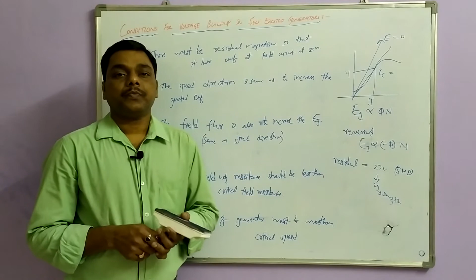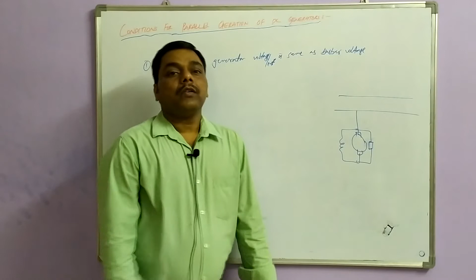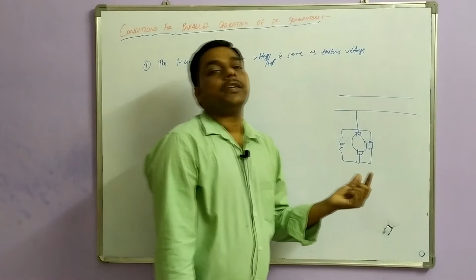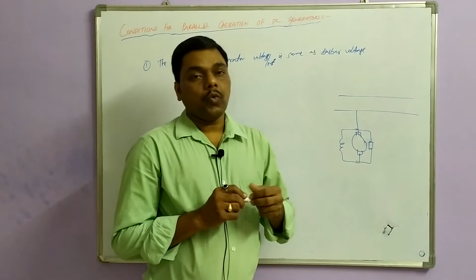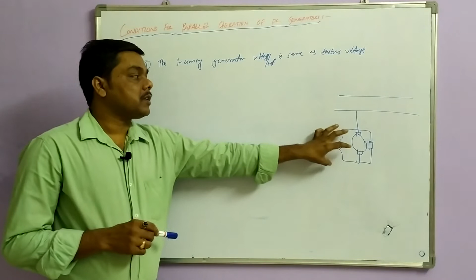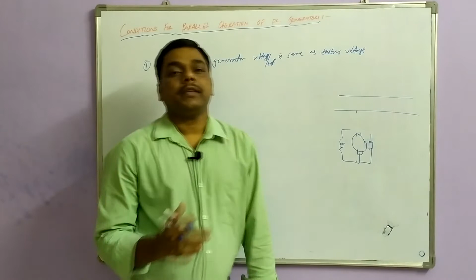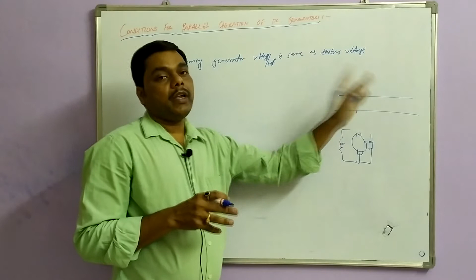The main conditions for connection of DC generators in parallel: the first one is that the incoming generator's induced EMF is the same as the busbar voltage. Since it is a generator, you can call it EMF. Suppose these are the two busbars we are operating and we have connected one generator here, which is going to supply. What is the voltage across this generator to connect it to the busbars? If both voltages are the same, this DC generator will synchronize very easily, that means it will match the corresponding busbar voltage. Otherwise there are circulating currents and fluctuations in the generators.